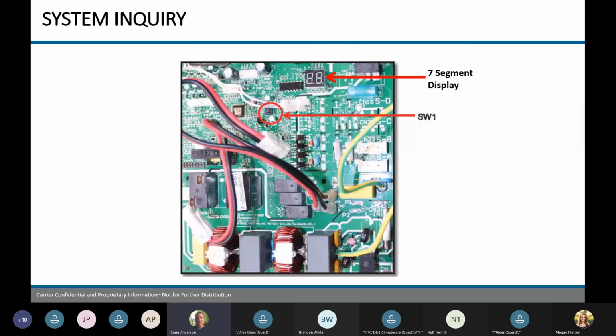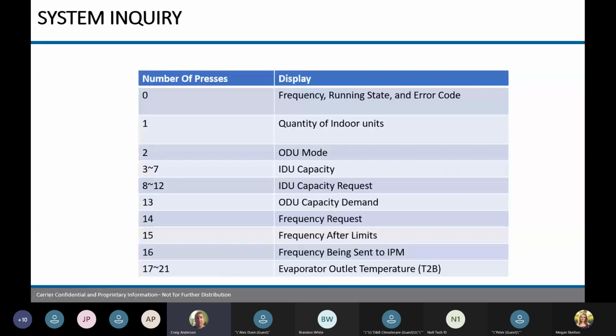So system inquiry can be done on the outdoor unit as well. On some of the boards, it'll have a little SW1 switch, and then you'll have your little display up there that's going to tell you what mode you're in. So that one's done a little bit differently. It's the number of presses. So if you press that button twice, it's going to tell you the outdoor mode. It's going to tell you a frequency. So it all depends on how many times you press that button and what your display is going to read.